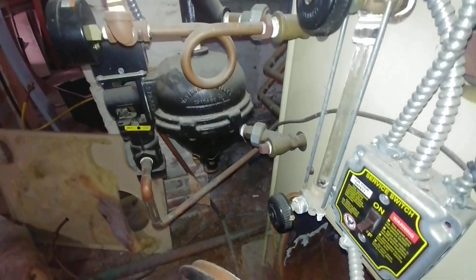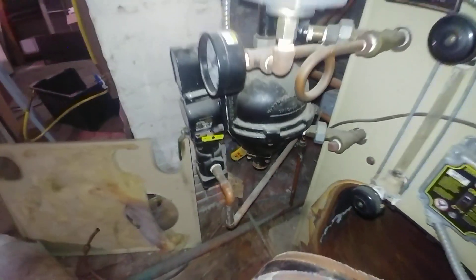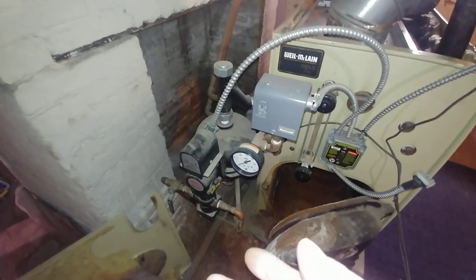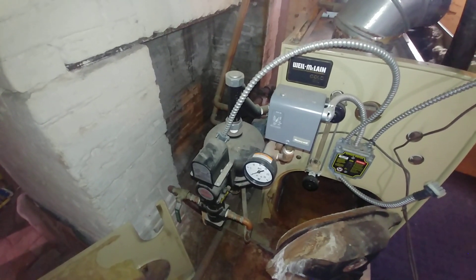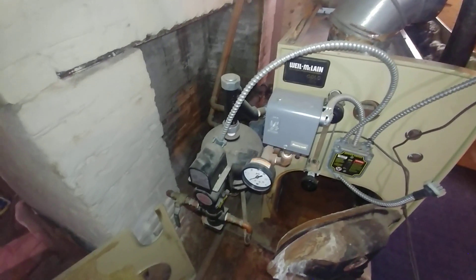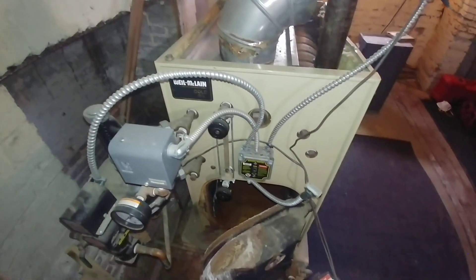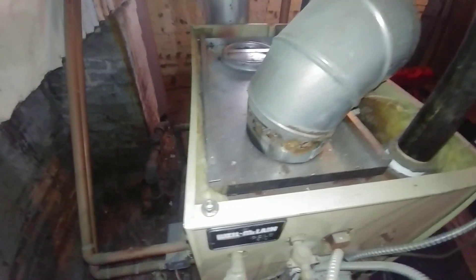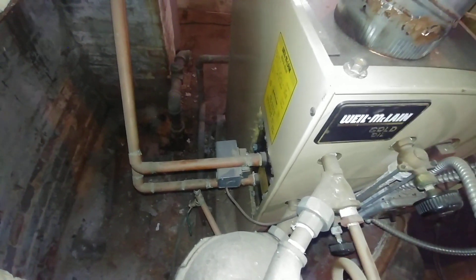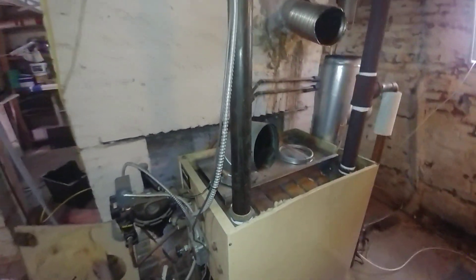The 47-2 automatic feeder just keeps feeding whether there's a leak or not — it doesn't care and doesn't alert you to a leak. So it just kept feeding, the boiler eventually rotted out, and then finally dry-fired. I think the summer/winter hookup coil has been abandoned.